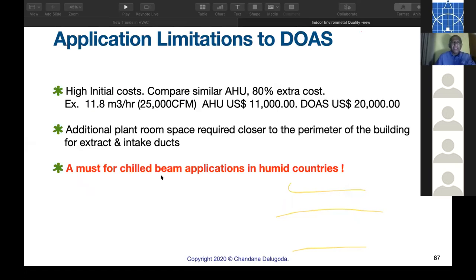High initial cost compared to similar AHUs, that's the only constraint, about 80% higher cost. Additional plant room space is needed, but it is a must for chilled beams in humid countries. Not even chilled beams, high latent load, like, let's say, large restaurants. Now hotels. Earlier they called it a 24-hour restaurant. Now it is called a different name though. So 24-hour operation, large restaurants. These are the best for DOAS, dedicated outdoor air systems.